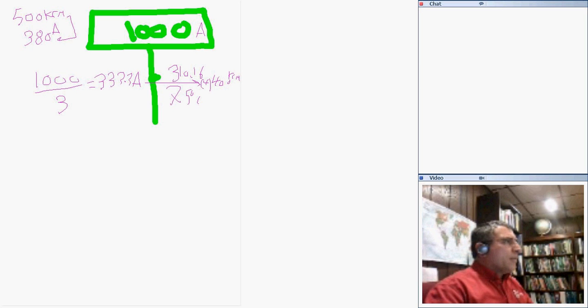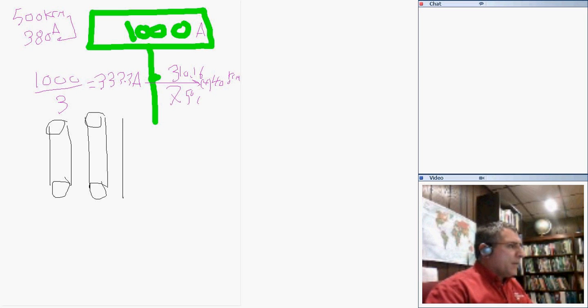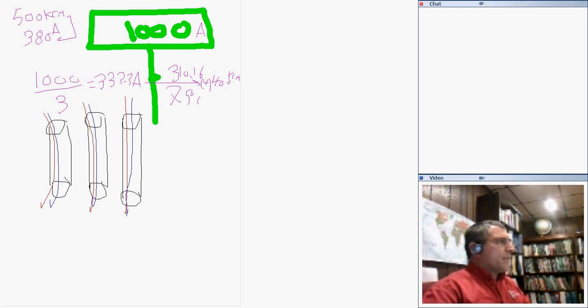So what does that mean, guys? What that means is I have my conduit number 1 here, conduit number 2, as you can imagine, and here's my number 3. That's the 3 runs, 3 sets. And inside each conduit, I'm going to take phase A, phase A, phase A, phase A, and then I'm going to get my phase B, my phase B, my phase B, and my phase B, and you can imagine what comes after B. You're going to get your phase C. Here's my phase C, my phase C, and my phase C. And not to leave my neutral alone, I grab my neutral in each one of them.